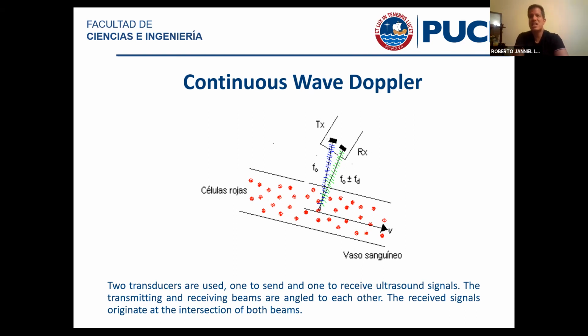If you buy a really cheap made ultrasound scanner, it can probably produce echographic images, but if you're guessing that you can get Doppler images from it, that's never going to happen. And it just doesn't happen because you need really good instrumentation. You need really clean amplifiers, and really good-looking transmitters that would send a signal that you can actually receive, amplify, and process. And that's going to be a really weak signal. You need a huge dynamic range. So really cheap scanners are just not going to make it. You need something a little bit more expensive than that.